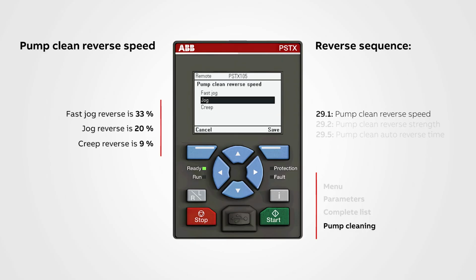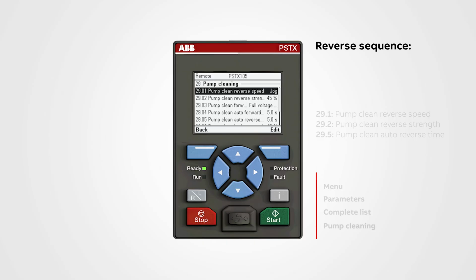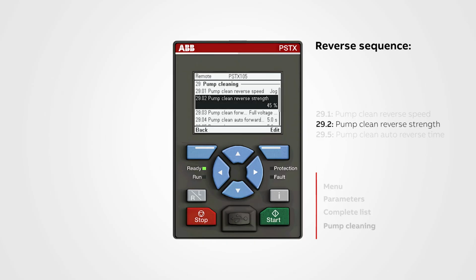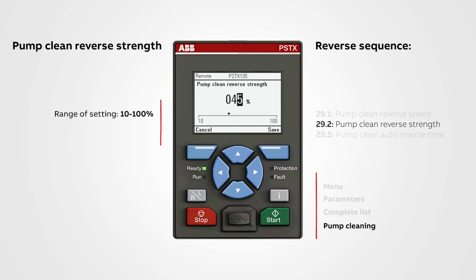Set this parameter to the speed you would like the motor to reverse at, but remember that the maximum reverse speed is 33% of the nominal motor speed. Next is the 29.2, pump clean reverse strength. This parameter is related to the torque that is generated during slow speed in the reverse direction. Choose a suitable value for the application. Too high a value could cause oscillations, and if too low, the motor may not start. The range of setting is between 10 to 100%, but the default value is 45%, which is a good starting point.